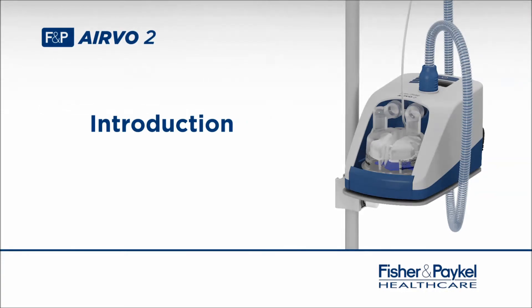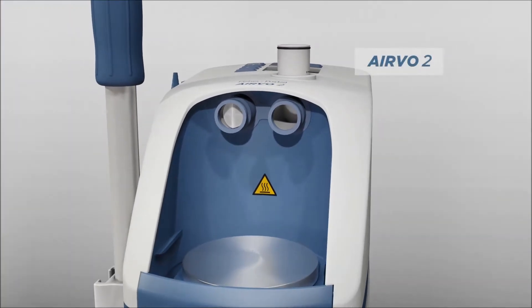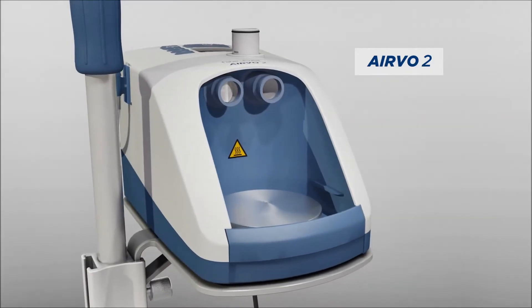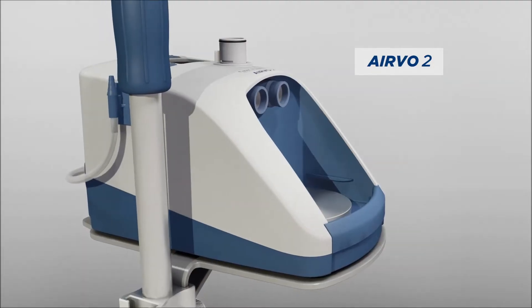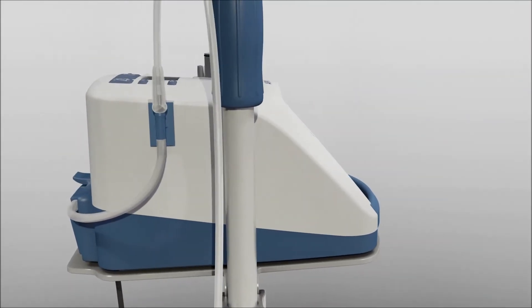The Airvo 2 is a humidifier with integrated flow generator that can deliver high-flow, warmed and humidified respiratory gases to spontaneously breathing patients through a variety of patient interfaces. The Airvo 2 system consists of the Airvo 2 humidifier, which can deliver humidified respiratory gases at flows from 2 to 60 litres per minute and oxygen concentrations from 21 to 100 per cent.